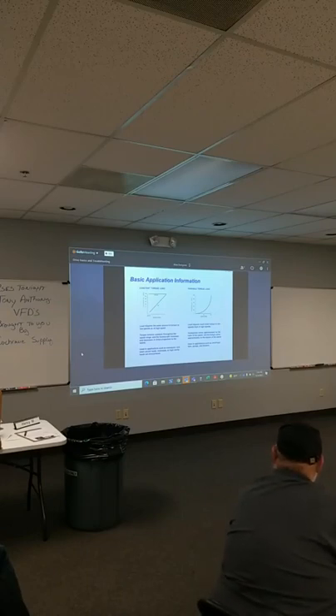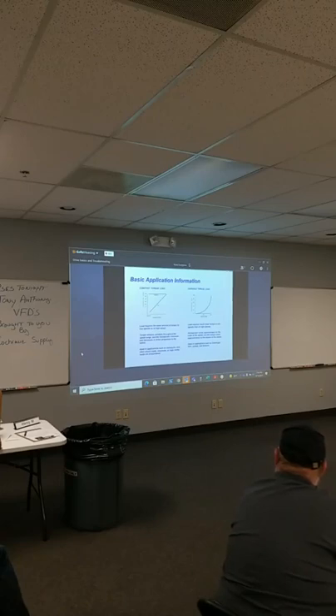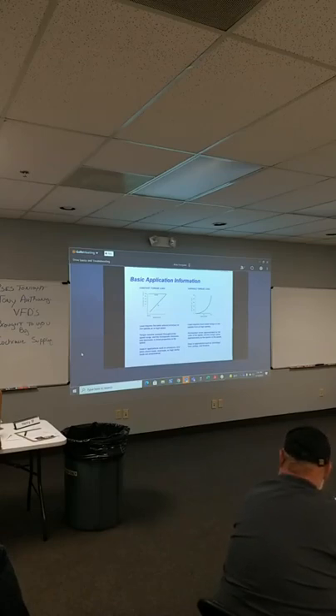So we get that question all the time: can I go faster than 60 hertz? If the motor can handle the extra load and the drive is sized for the extra load, then you've got to look at the fan or the pump curves to make sure that at some point you're not going to increase flow and it's going to go away. You can also do that by touch and feel if you want to: keep slowly increasing it and see at what point you lose flow. But once again, the motor usually has to be oversized in those applications.